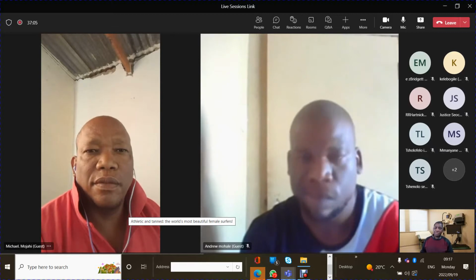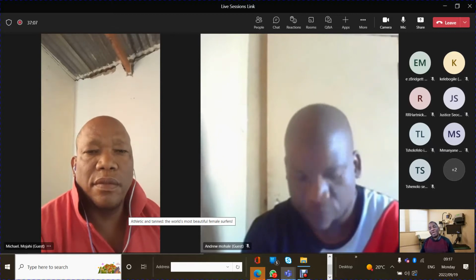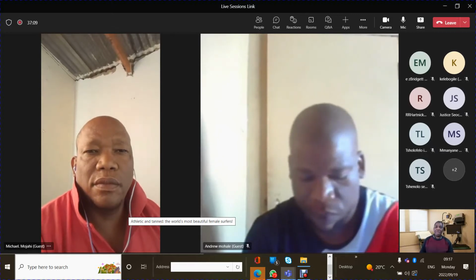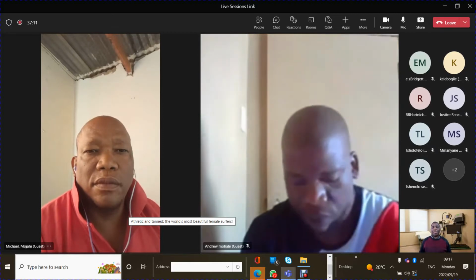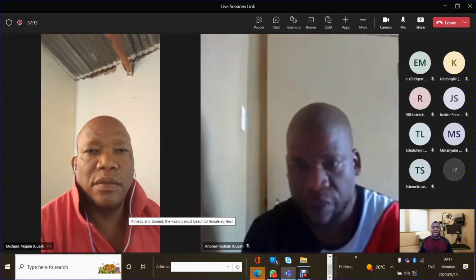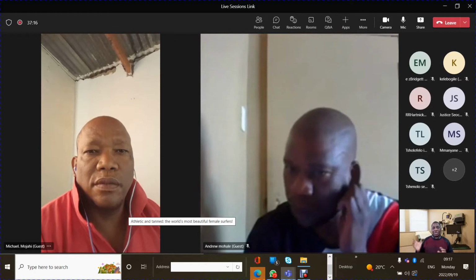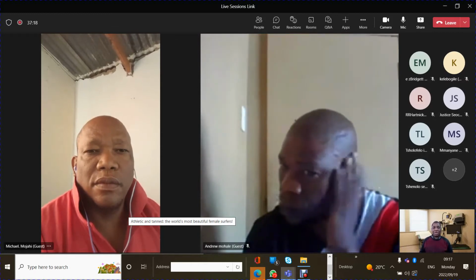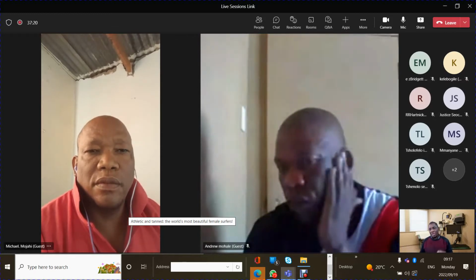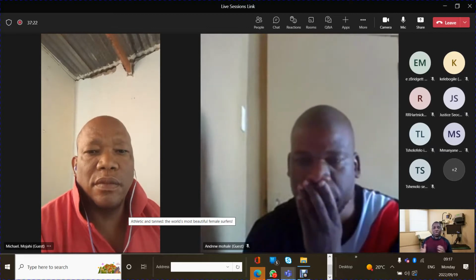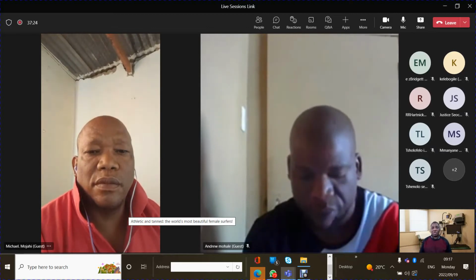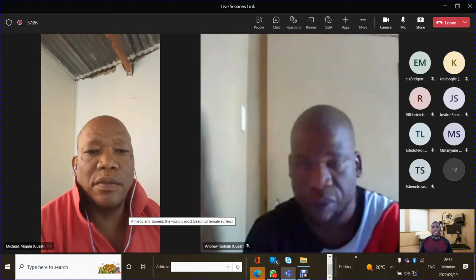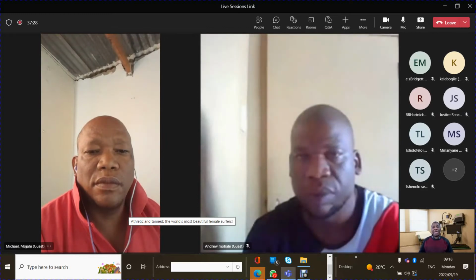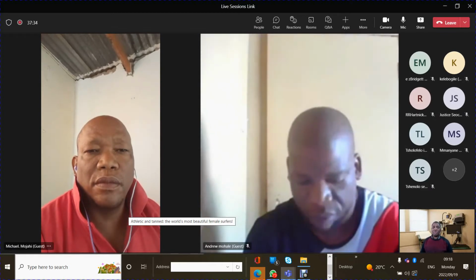Secondly, when you do your preventive maintenance, every time you do preventive maintenance, apart from testing that the equipment is working correctly, the calibrations are in order, you're getting correct results when you test with the analyzer, you need to do an electrical safety test to make sure it is still safe for use. That is your job as a clinical engineer. You cannot excuse or outsource that. The responsibility rests with you to make sure that that device is safe for use.